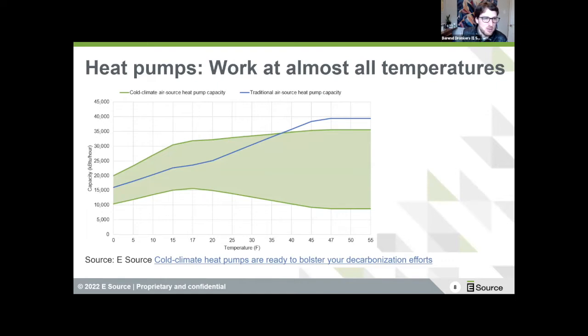This is from some work we recently did. The blue line is the capacity of a traditional air source heat pump, which drops off significantly once you hit 35 degrees Fahrenheit. The wider band reflects that this is still a developing technology, with some cold climate heat pumps performing at higher capacity than others. Generally, capacity doesn't really start dropping until you hit 15 Fahrenheit, and this keeps improving—some units we're aware of can maintain 80% capacity as low as -17 Fahrenheit.